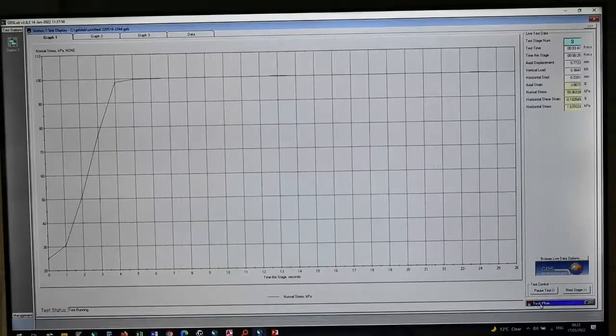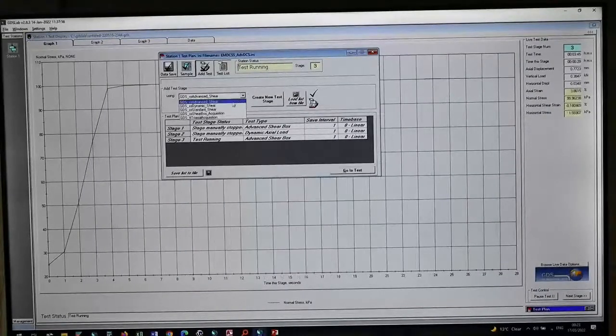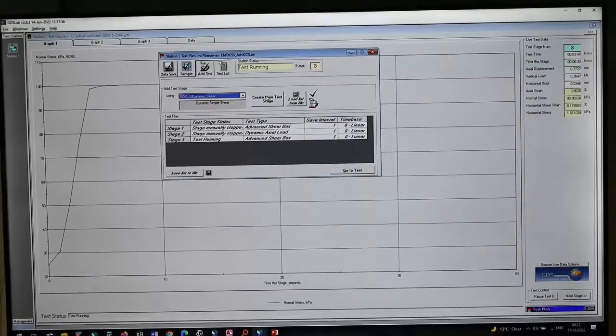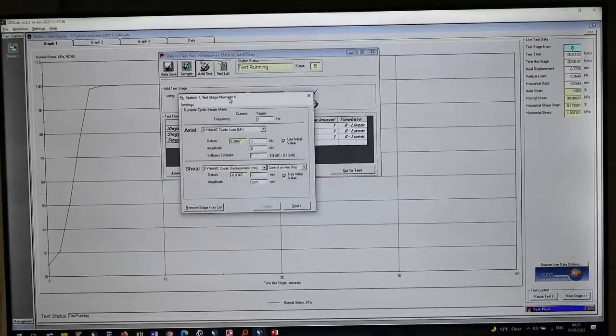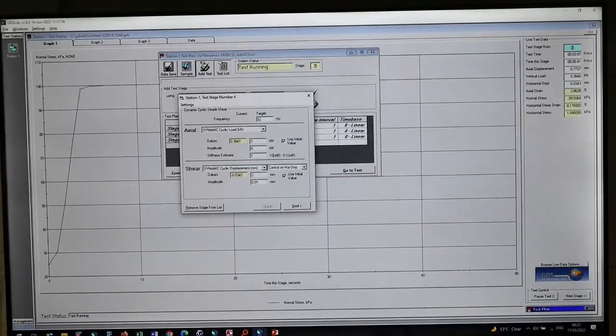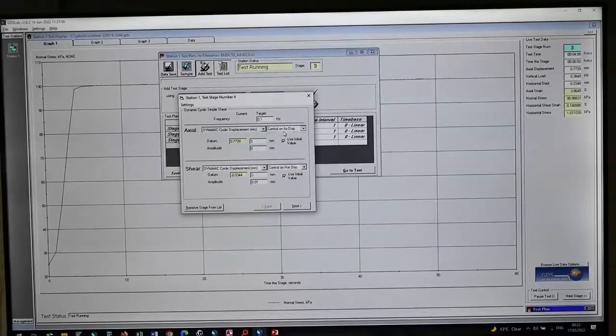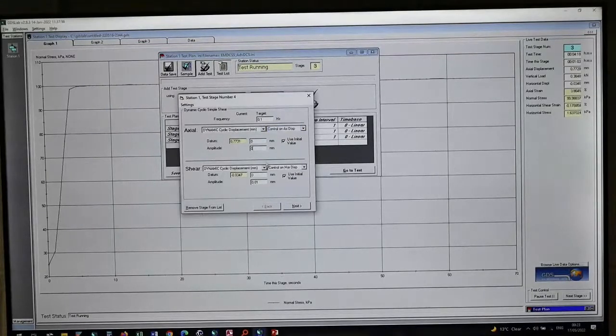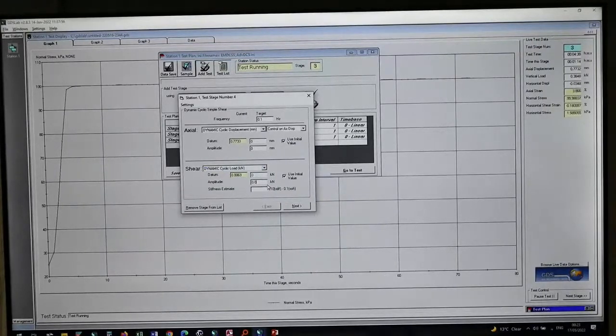While that runs, I will go to the dynamic shear stage and define my test conditions for the constant volume cyclic simple shear test and explain a few tabs here. For the constant volume cyclic simple shear test, I'm going to use a frequency of 0.1 Hertz. In terms of axial control, it will be a displacement control. So I will keep the current axial displacement value so that the test is run as a constant volume test. And for the shear one, I'm going to put a cyclic load, which is going to be a CSR value of 0.15. I'm going to put a value of 1 here.